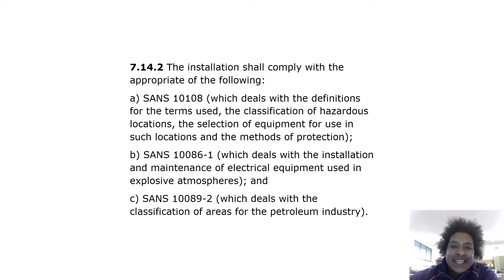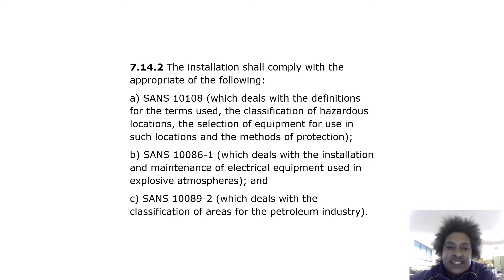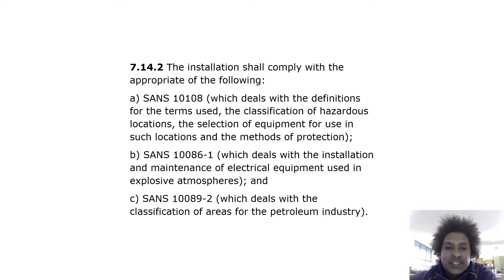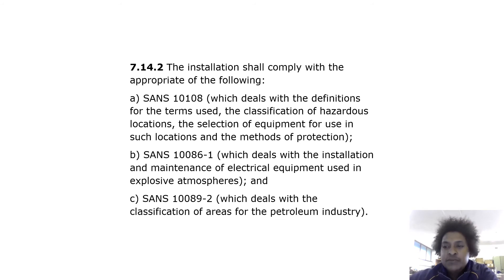The installation shall comply with the appropriate of the following: SANS 10108, which deals with the definitions for the terms used, the classification of hazardous locations, the selection of equipment for use in such locations and the methods of protection. SANS 10086-1, which deals with the installation and maintenance of electrical equipment used in explosive atmospheres, and SANS 10089-2, which deals with the classification of areas for the petroleum industry.